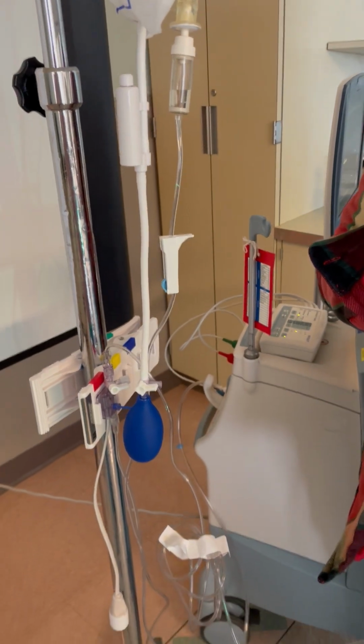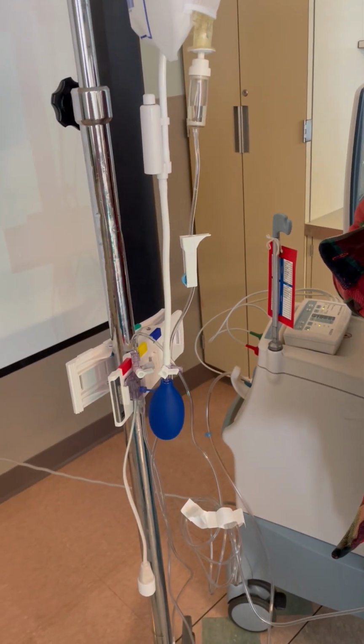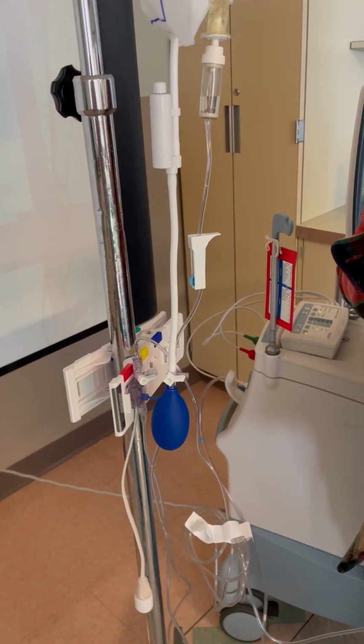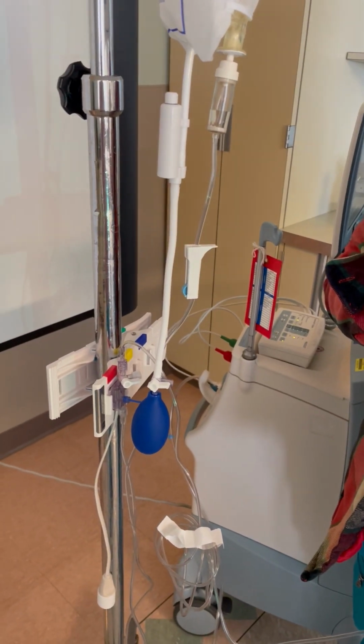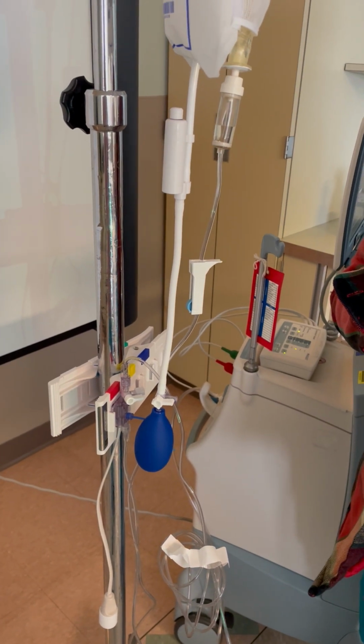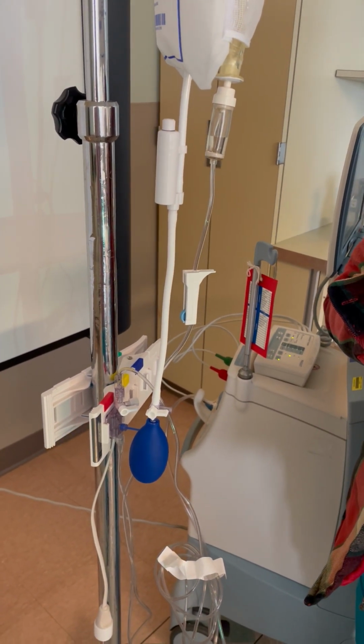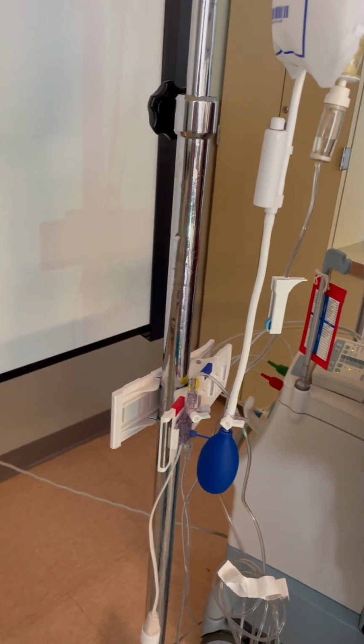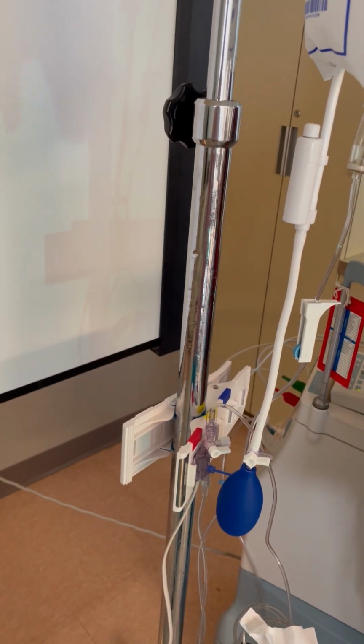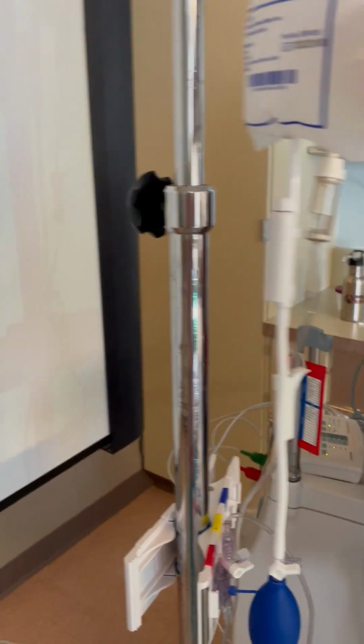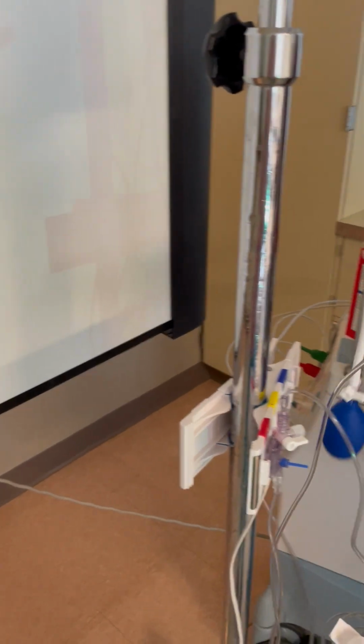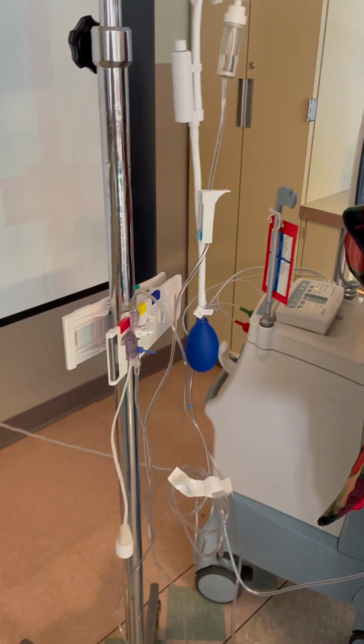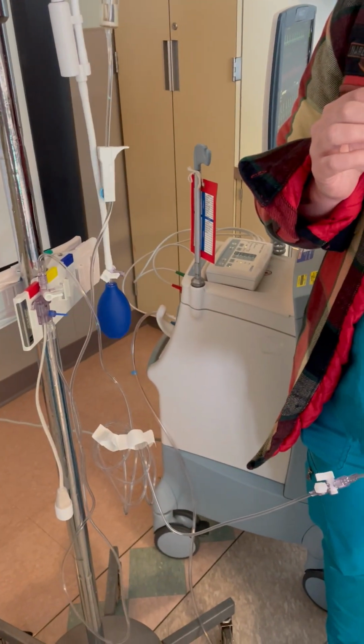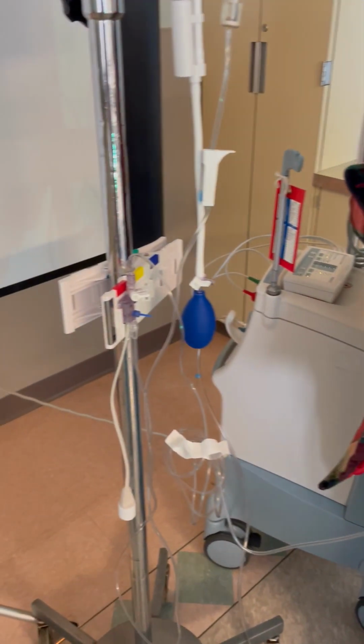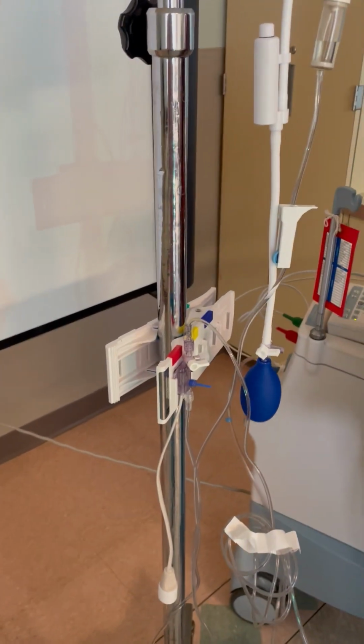So if your arterial line is dampened, if it is not showing you a proper waveform on the balloon pump screen, what you're going to want to do is troubleshoot it exactly like you would troubleshoot an A-line. So we would want to, first of all, check all of our connections. Do we have tight connections all the way through the system? Do we have our bag pumped up to 300 millimeters of mercury? Is there fluid in our bag? Are all of the roller clamps open? Do we have any kinks in the line related to where our patient's position is? So make sure that their leg is nice and straight. Make sure that there's no restrictions in the catheter.